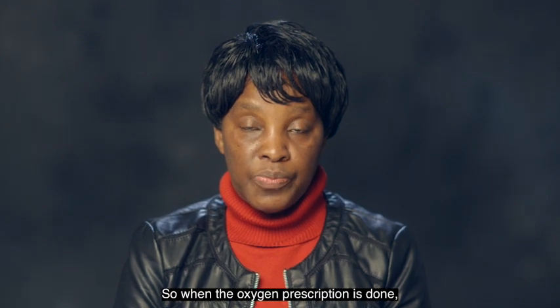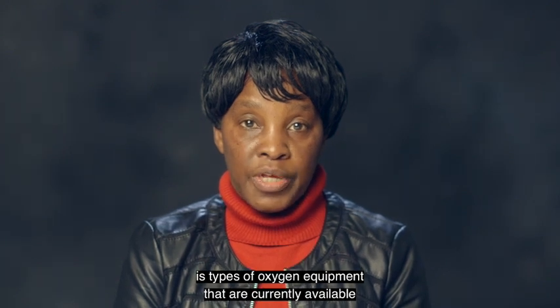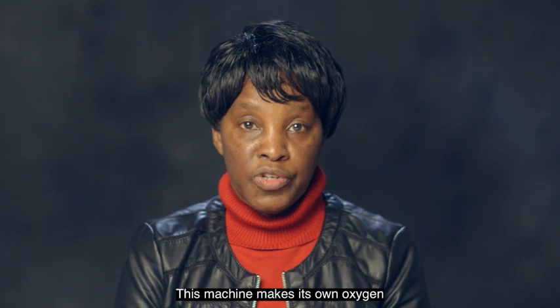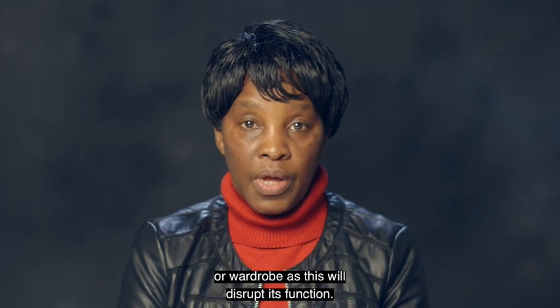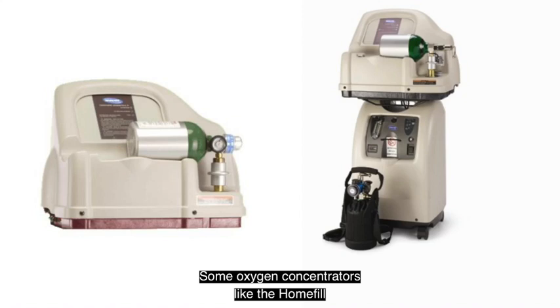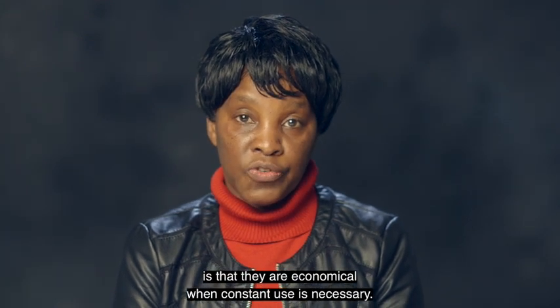When the oxygen prescription is done, the next thing to look at is types of equipment. The oxygen equipment currently available on the Irish market includes the oxygen concentrator. This machine makes its own oxygen by extracting it from the air, and as such it requires enough room for air circulation. It should not be placed in an enclosed space or wardrobe as this will disrupt its function. It can deliver up to 95% oxygen at one litre per minute, but concentration drops to around 84% at four litres. Some concentrators, like the HomeFill, enable you to fill your own ambulatory oxygen cylinders. Concentrators are economical when constant use is necessary.